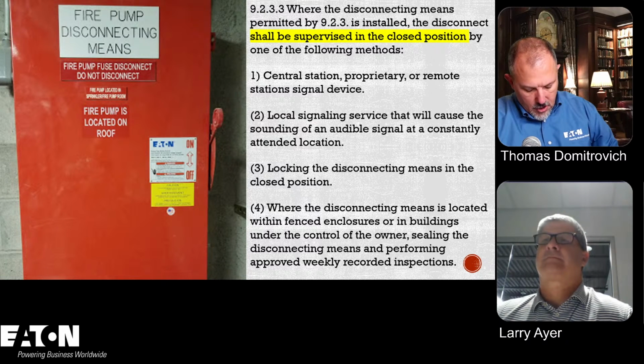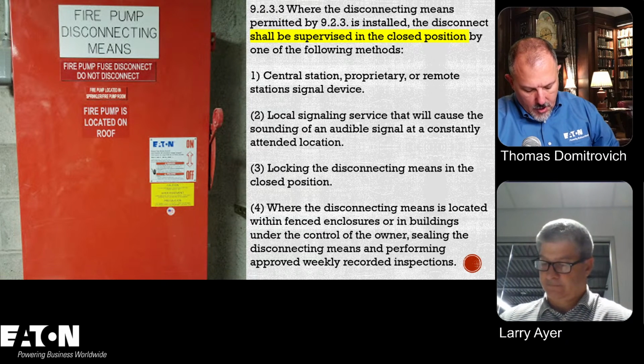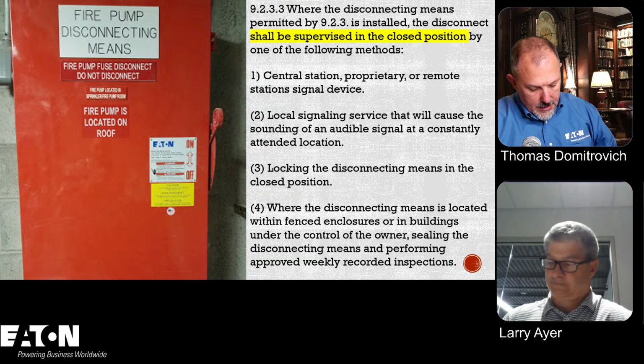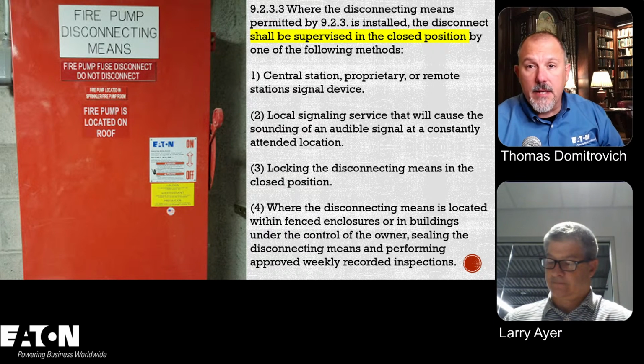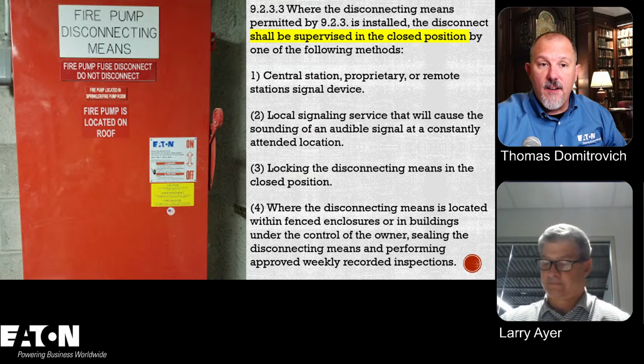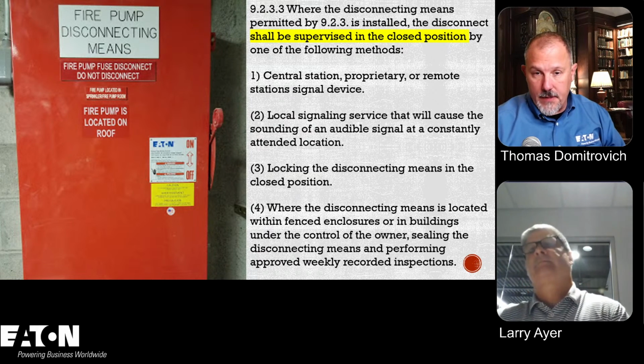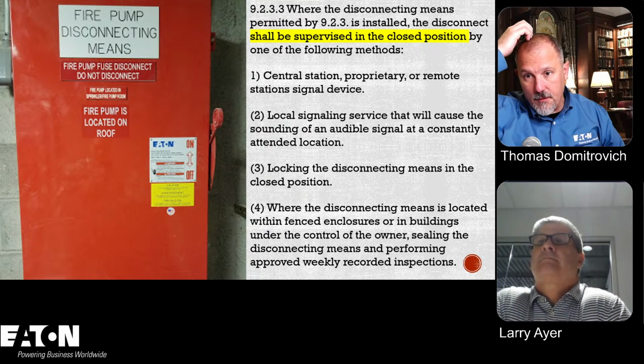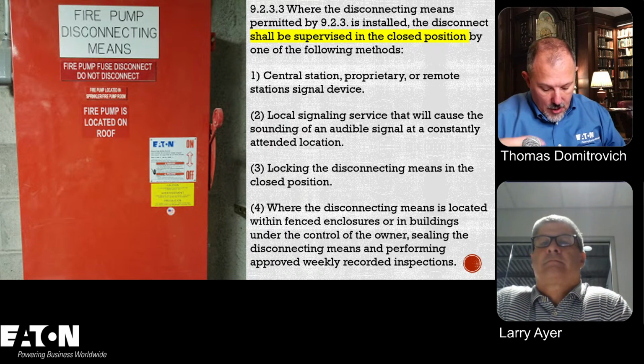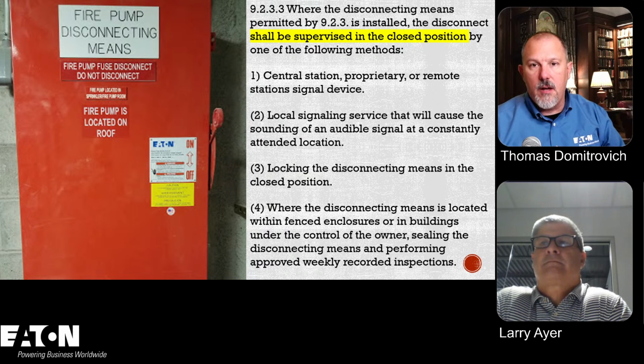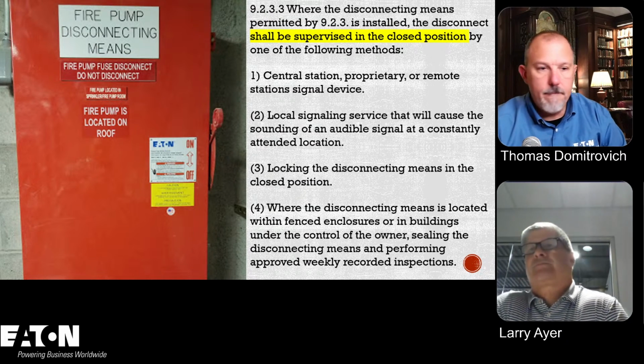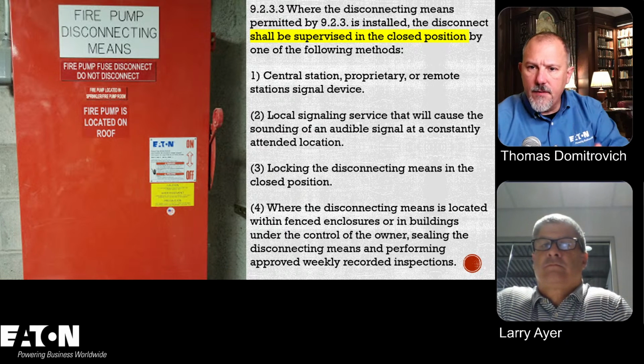Yeah, it says selective coordination. Overcurrent protective devices shall be selectively coordinated with all supply side overcurrent protective devices, and that's only in the multi-building campus style complex. If you're coming directly off of the service, you've got one overcurrent device. Now, to your point, you might have some other things inside of the controller, but the only place where there's a selective coordination requirement is when you're dealing with a multi-building campus style complex and you're employing the feeders and whatnot that you would have in those types of applications. Correct. Right. All right.